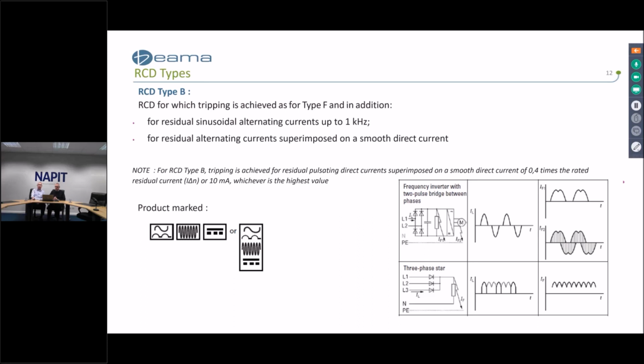And again, in terms of identifying the product, they will be marked, as you can see on the screen, by either the side-by-side boxes or the one box with the waveforms above each other. And this shows basically the Type AC symbol, the Type F symbol, and the DC symbol, which is for Type B.